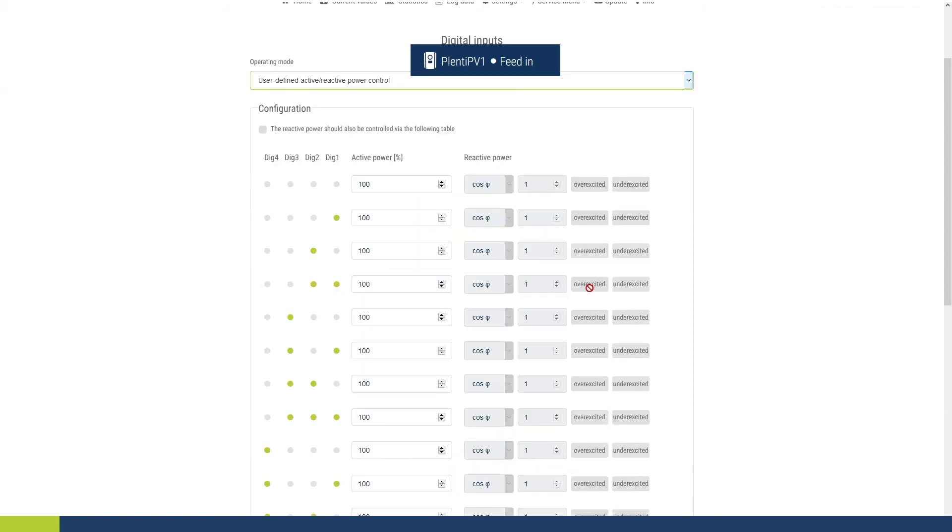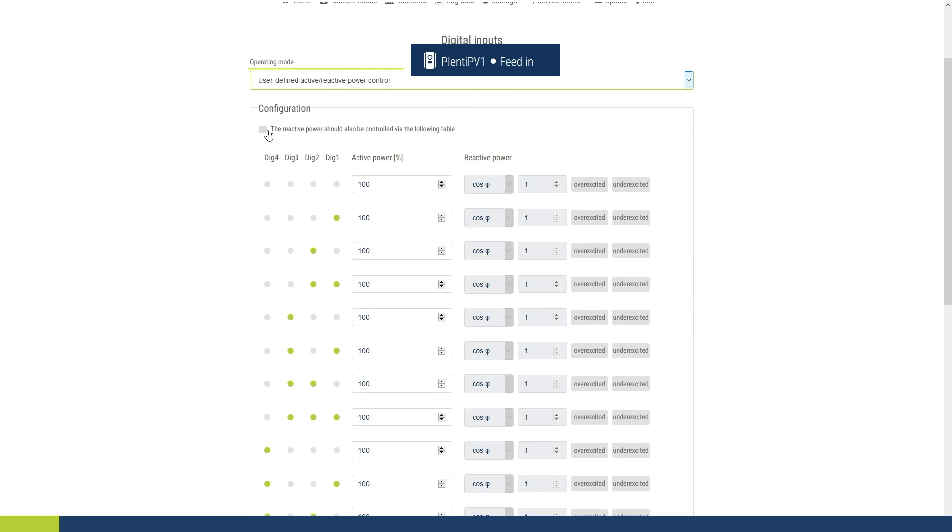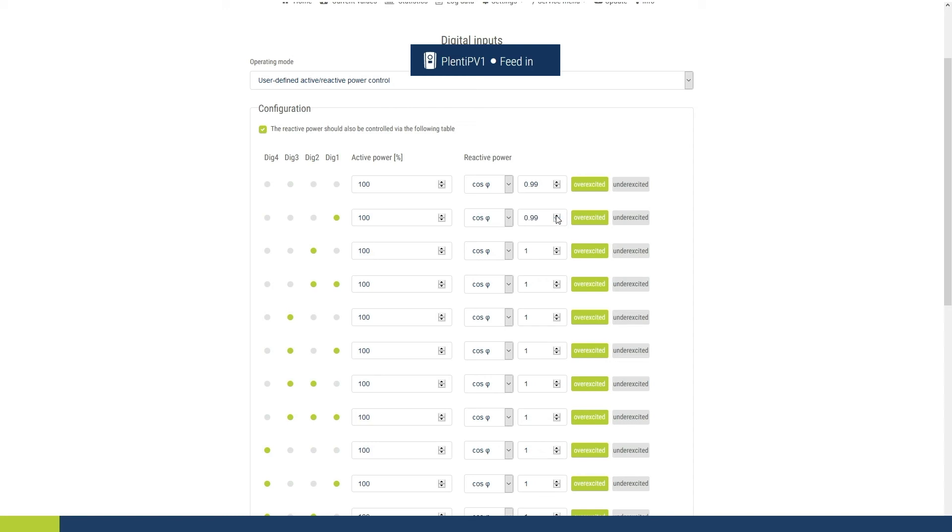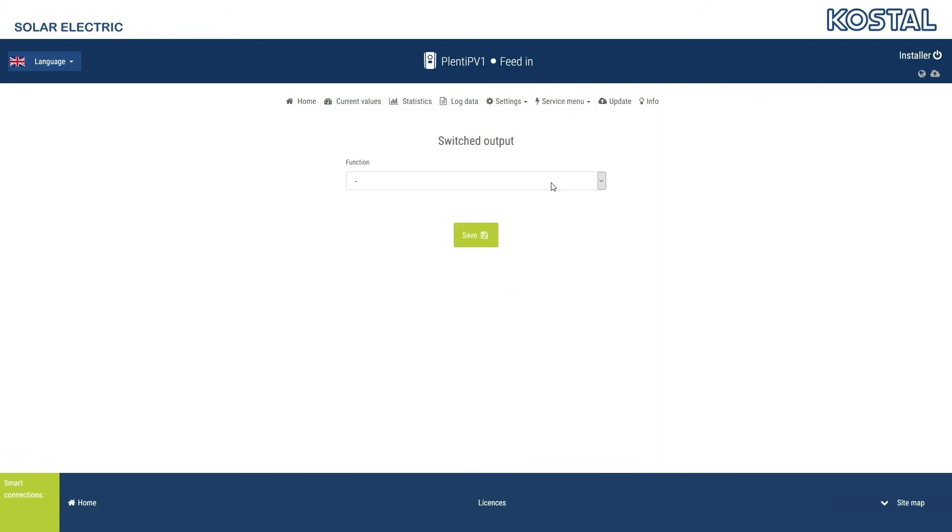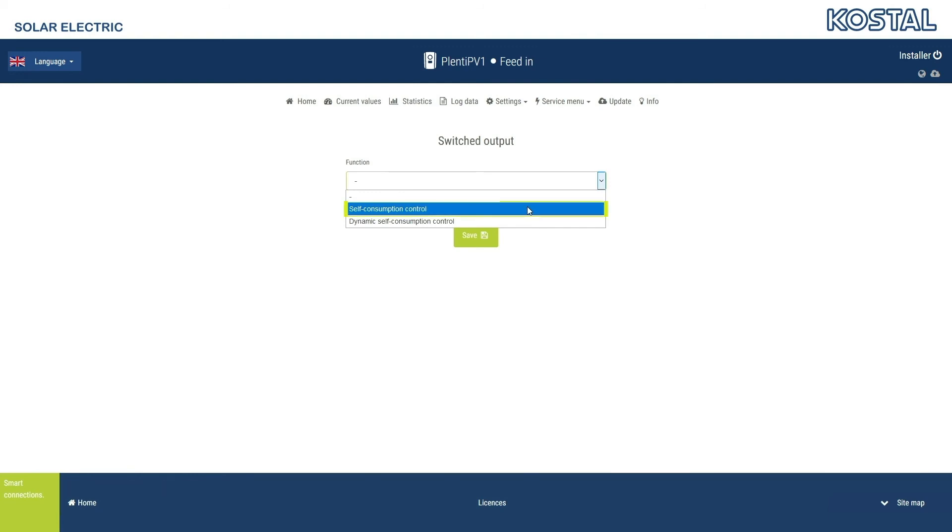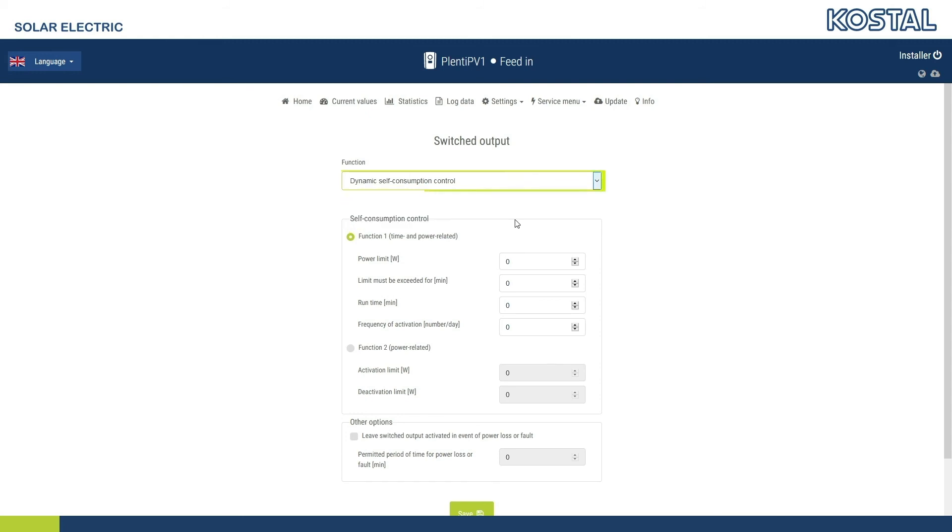The settings for the User Defined Active slash Reactive Power Control operating mode can be configured individually. You will usually receive the relevant requirements from your energy provider. In the Switched Output menu, you can set the Switched Output function on the Smart Communication Board. You can choose between two functions and individually set the activation and deactivation conditions. The Self-Consumption Control function relates to the output power of the inverter. Dynamic Self-Consumption Control is only possible in conjunction with an energy meter and relates to the power at the grid connection point.